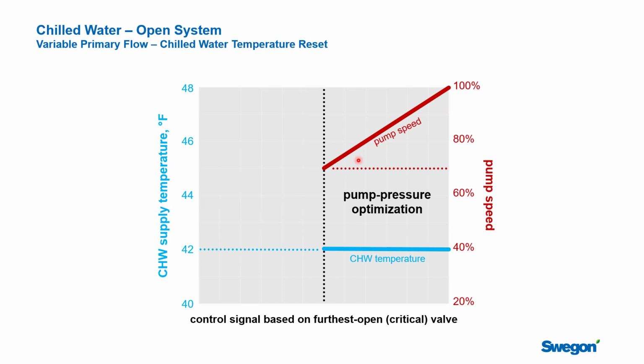But as we get down closer to, let's say, 70%, the next step is to say, okay, we're actually going to hold the pump speed even here, and then we will modulate the chilled water temperature instead to take the load off of the chillers for this lower flow rate. And this will work well. It helps you solve the problem of, do you want to send out a little bit of very cold water or a whole bunch of warmer water, and you've got to decide where you want your savings, from the pump or from the chiller. This is an algorithm that allows the programmer for the building automation system to decide how to do that. You just have to remember that as you start to reset this temperature, you have to do it in such a way that you maintain your dew point in the space.